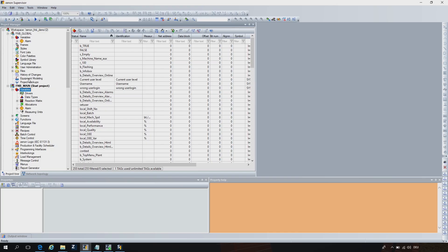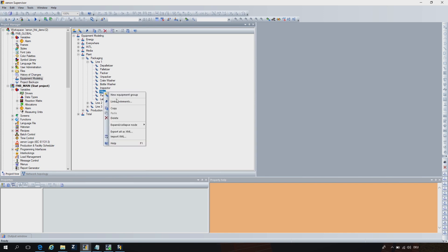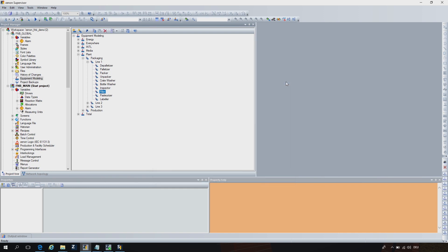Then we have a list of tags. What is interesting is that already in this phase you can contextualize the data — to make clear where the data is coming from. For this purpose, we have in zenon equipment modeling. We can describe an asset model here, and you can do it following ISA 95, for instance, to describe all the structure. This structure and contextualization you can use everywhere in your project. You can put here everything you may need — many components, many elements. This is a very first step to give a data point, a single piece of information, some context: to know where it is, to know what it is, whatever the meaning is.